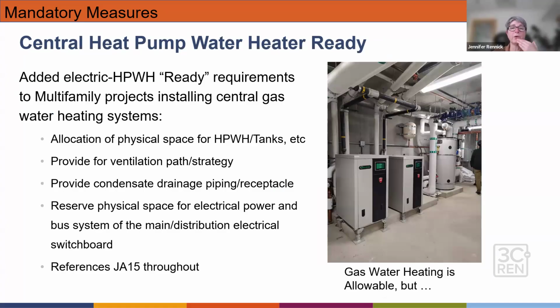So back to the central heat pump water heater system. Gas water heating is allowed, but now to be electric ready, you're going to have to allocate the physical space for those heat pump water heaters and the tanks. You need to provide for the ventilation pathway and strategies, depending on the type of system. You need to provide the condensate drain piping and receptacles, and then you need to reserve that physical space and the electrical power for the electrical system. And then this code section goes into more detail on each of those topics, but it also says you would provide this ventilation pathway to do XYZ per reference appendices JA15, and so on.